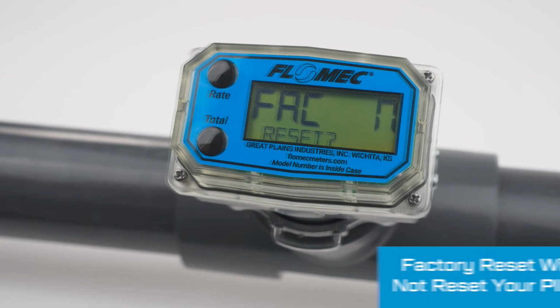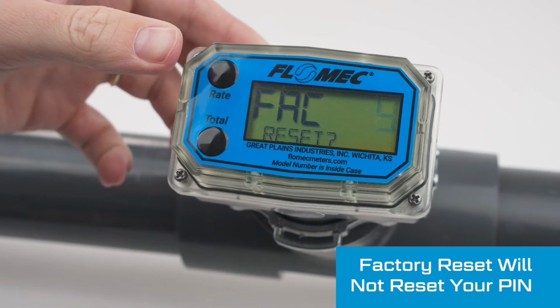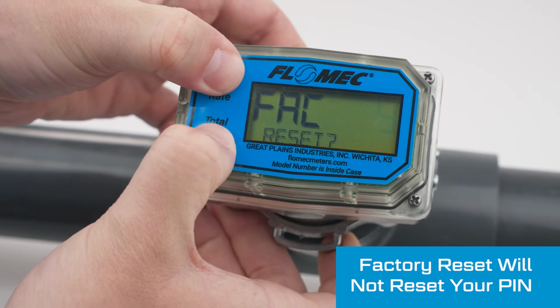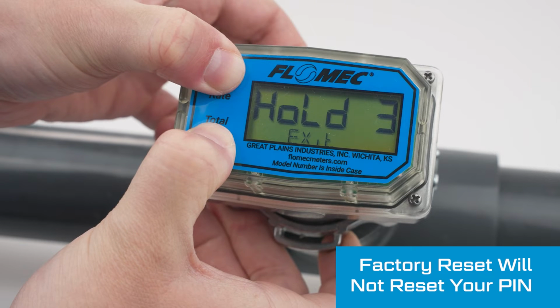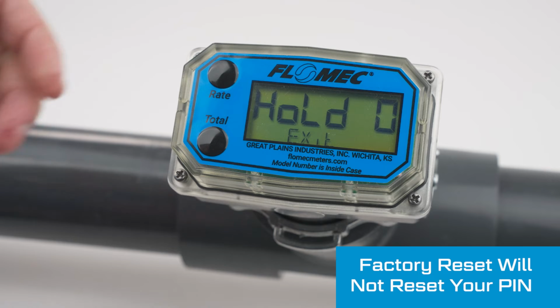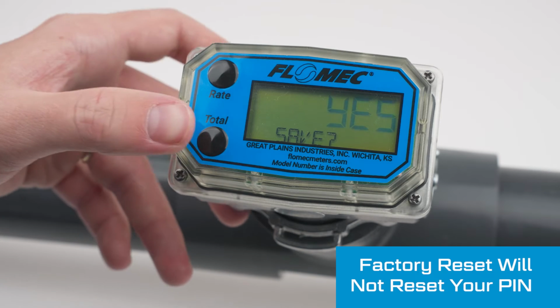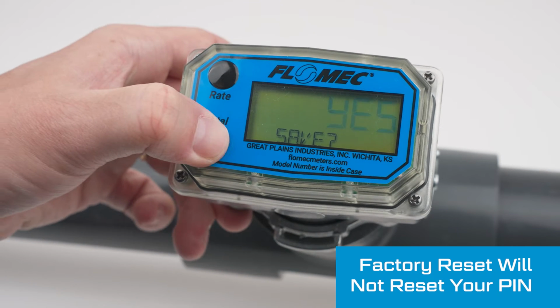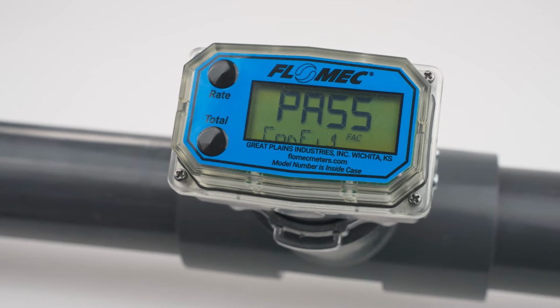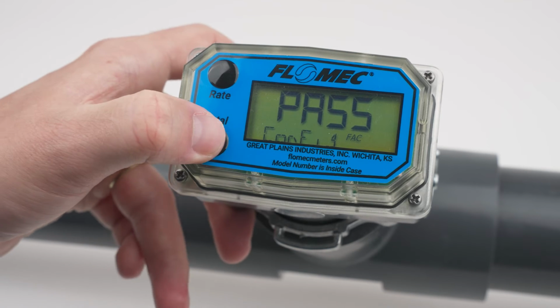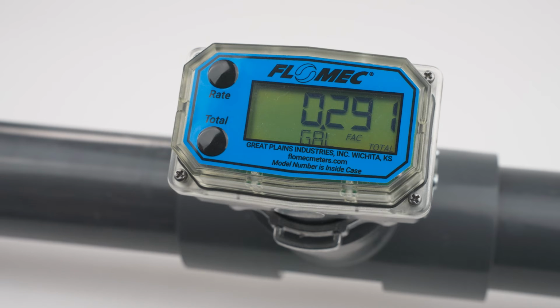If you want to reset the meter, select Yes, then hold the Rate and Total buttons for 3 seconds to exit the configuration menu. The meter will ask you to save. Press the Total button twice to save and complete the factory reset. The meter will display Pass Config to indicate a successful factory reset. Press either the Rate or Total button to return to normal operation.